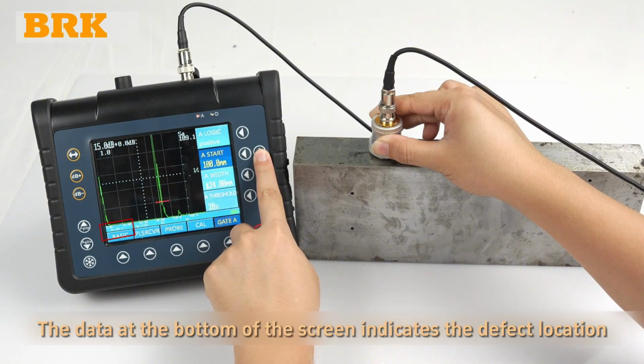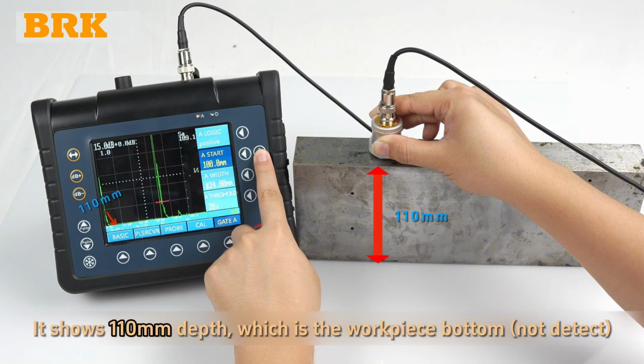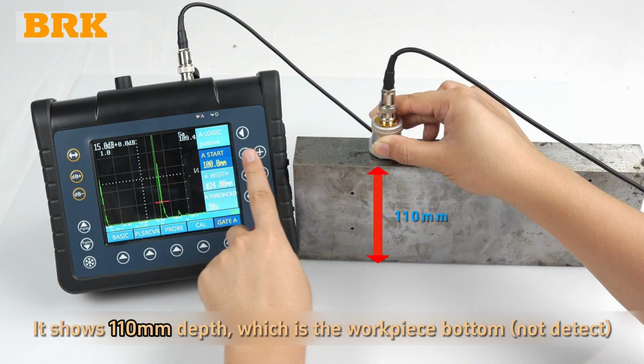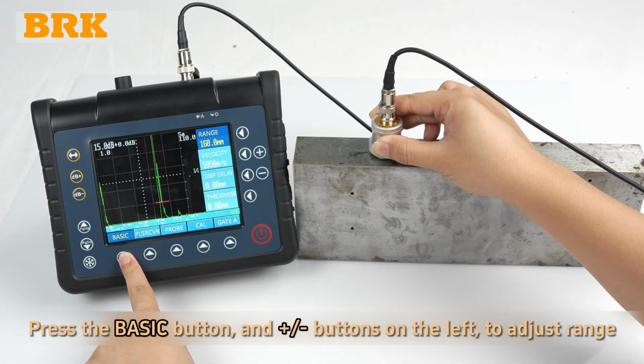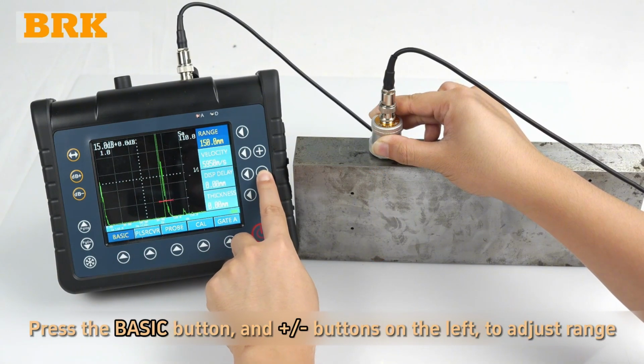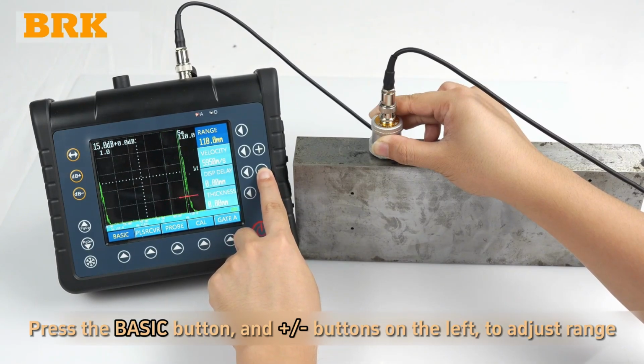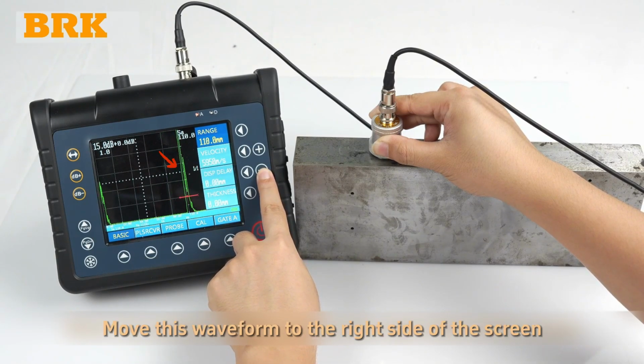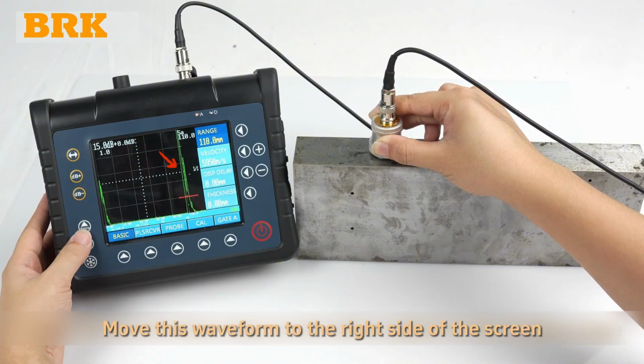The data at the bottom of the screen indicates the defect location. It shows 110 mm depth, which is the workpiece bottom, not detect. Press the basic button and plus or minus buttons on the left to adjust range. Move this waveform to the right side of the screen.